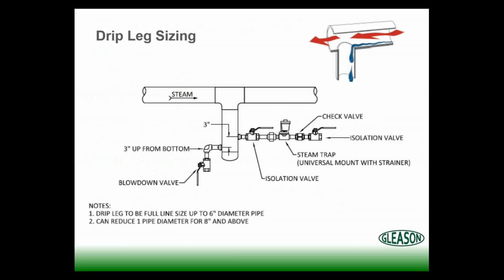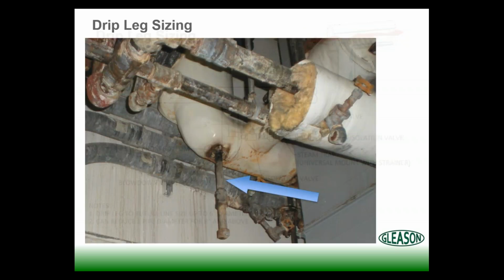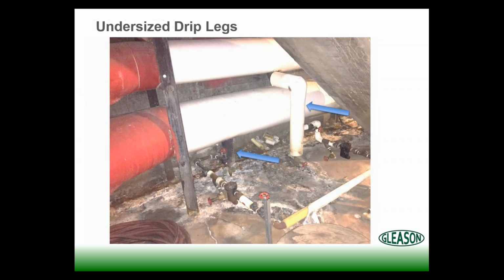Okay, so showing the proper sizing of a drip leg. If our steam header is 6 inches, our drip leg diameter should be 6 inches. Once we get to 8 inches and above, one pipe size below is acceptable. Here's an example of an unacceptable. Here's our steam header that we've got our drip leg coming off of. Drip leg is dramatically undersized there.